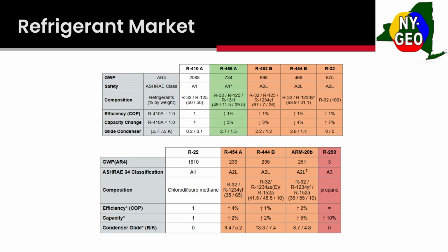On the other hand, R32 is a non-proprietary refrigerant. And there's plenty of R32 available in the market today. It is much cheaper. So for some perspective on pricing, R22, which I don't have on here, but it's right here. There we go. R22 for a 30-pound jug, $795 is the market rate. 410A, $175. 454B, $399, and R32, $255. So yes, R22 is still the king of expensive refrigerants, but 454B isn't exactly cheap either.